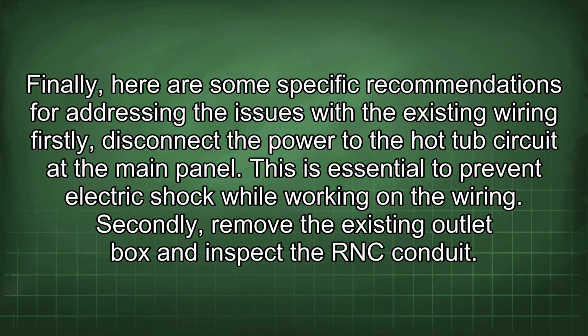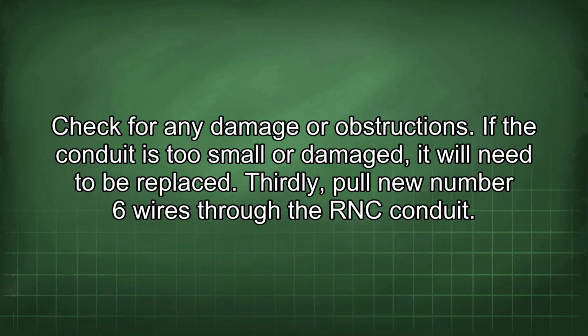Finally, here are some specific recommendations for addressing the issues with the existing wiring. Firstly, disconnect the power to the hot tub circuit at the main panel. This is essential to prevent electric shock while working on the wiring. Secondly, remove the existing outlet box and inspect the RNC conduit. Check for any damage or obstructions. If the conduit is too small or damaged, it will need to be replaced.